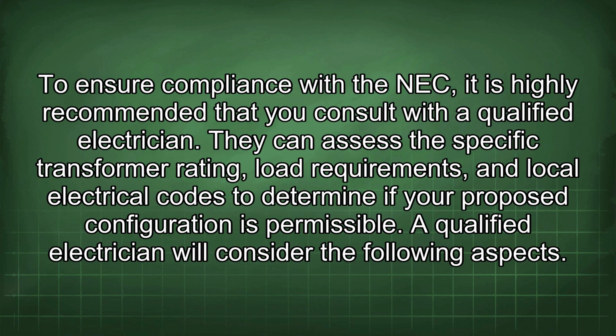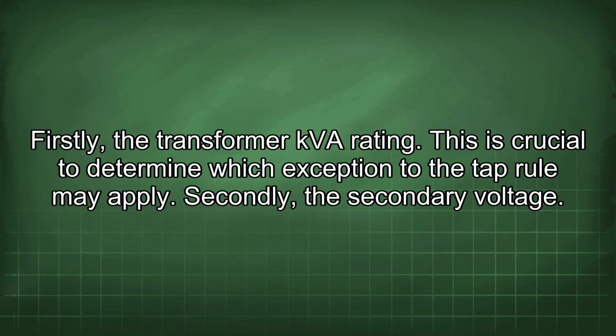To ensure compliance with the NEC, it is highly recommended that you consult with a qualified electrician. They can assess the specific transformer rating, load requirements, and local electrical codes to determine if your proposed configuration is permissible. A qualified electrician will consider the following aspects. Firstly, the transformer kVA rating. This is crucial to determine which exception to the tap rule may apply.